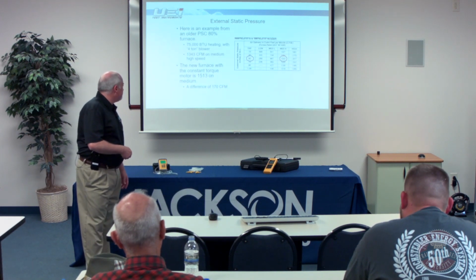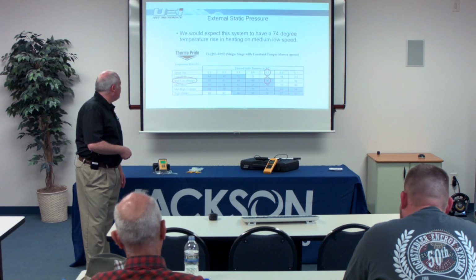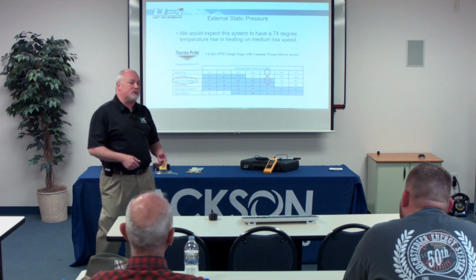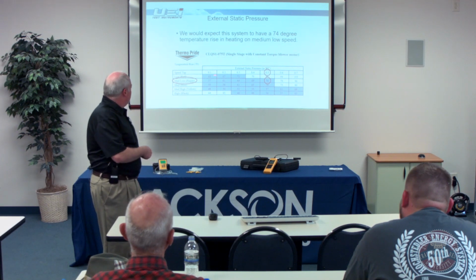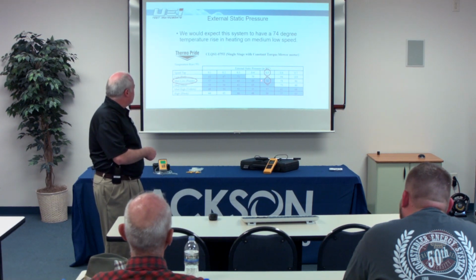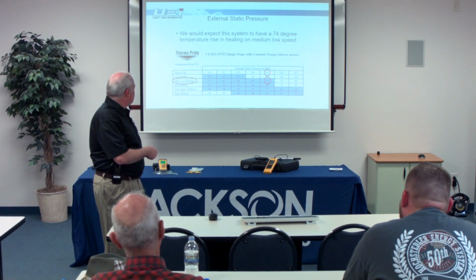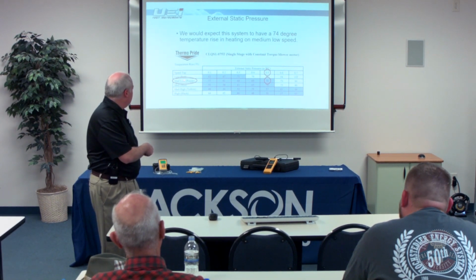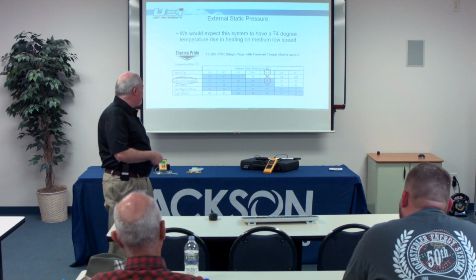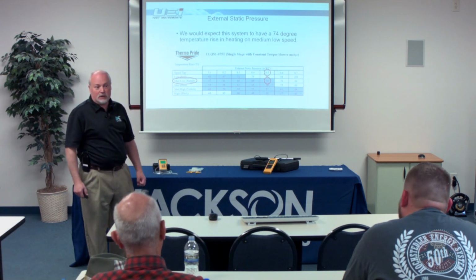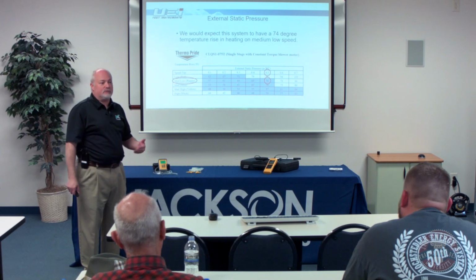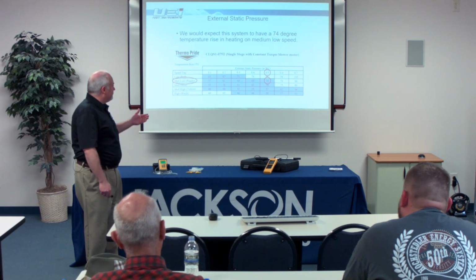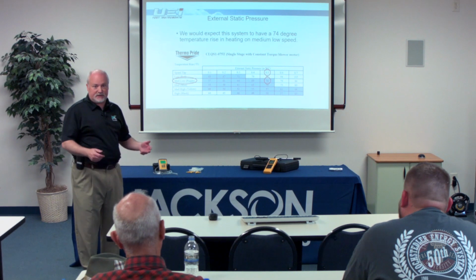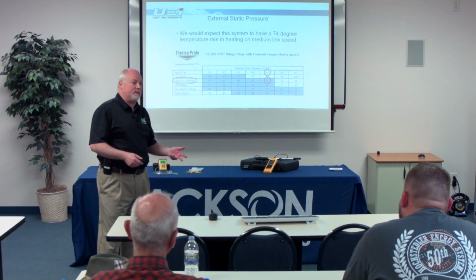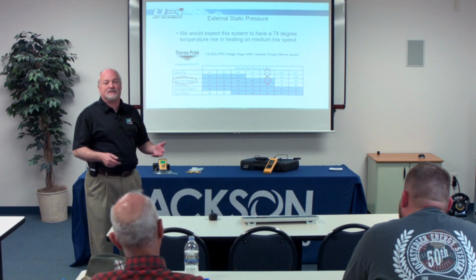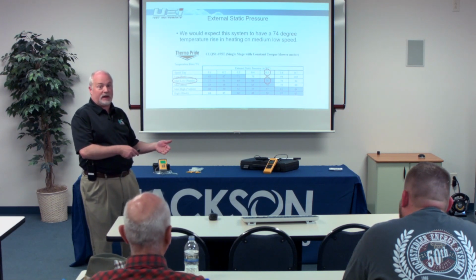Okay. The other thing that this can tell us, if we have external static pressure and we look at our airflow, it can also give us what our temperature rise is expected. In this particular case, 1/2 inch of static pressure on that medium-low speed, we'd be expecting a 74-degree temperature rise across it. So that gives us an idea to troubleshoot. If I've got an 80-degree rise instead of 74, I need to look for something. What else is going on in that system, because I'm not seeing what I would expect.